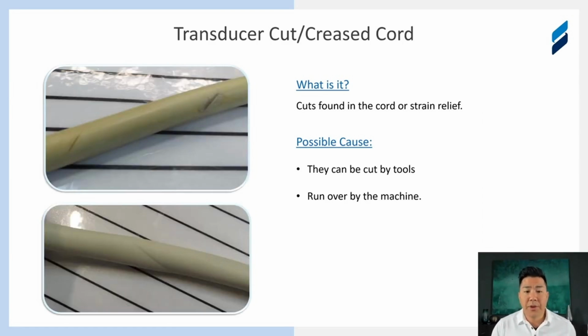The transducer failure we're looking at here is really a cut or a creased cord. So we have a transducer, and we're talking about the cord here. In this particular example, we've got a picture of some cuts, and the lower picture here is a crease. Pretty straightforward. With the cuts, something sharp got to it. Could be a surgical tool, could be accidentally hitting something hard and sharp. And the lower one, not really a cut, but a pretty severe crease, is oftentimes pinched in a door, run over by a machine, something like that.